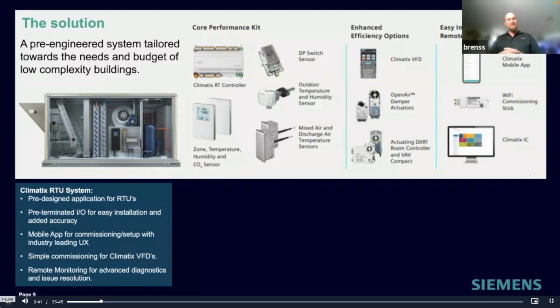So it comes with one Climatix RT controller. It comes with a choice of room unit, display or non-display. It comes with a differential pressure switch for a filter. We all know that filter changes are usually done on a quarterly or half-year basis, and sometimes they don't even need to be changed. This will tell you if it needs to be changed or not. It also comes with one combination sensor to be used for outdoor air temperature and humidity. It also comes with two regular sensors that you could use for mixed air and discharge air temperature. These are key ingredients to making sure the system works right.